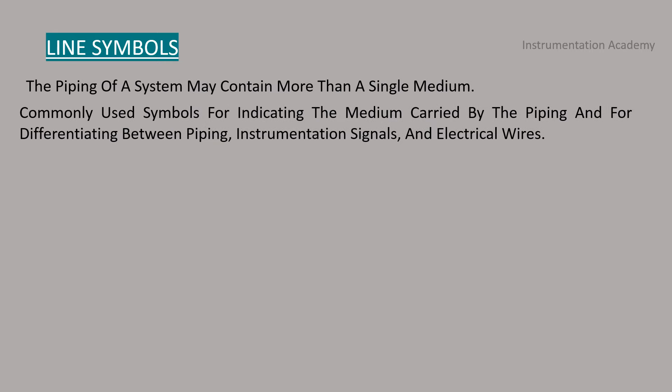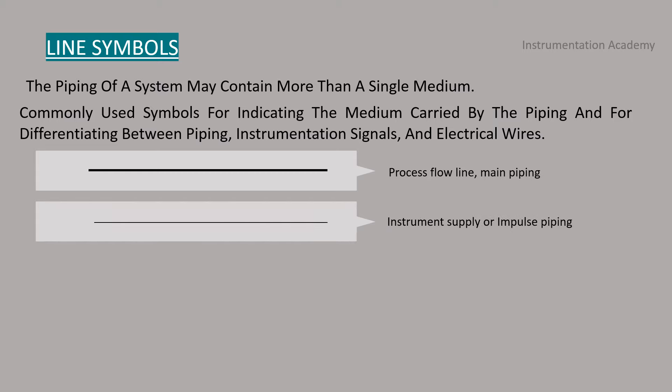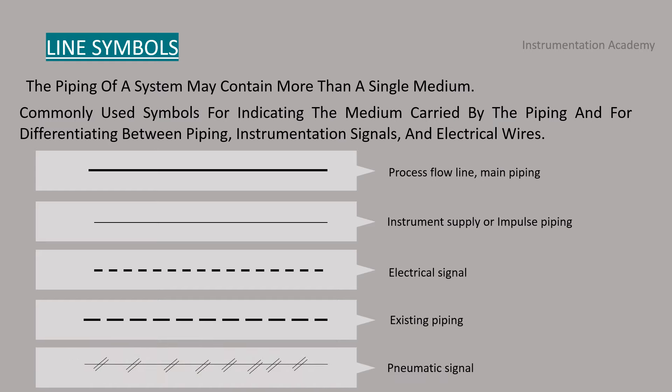The pipe system may contain more than a single medium. These are the symbols used for indicating the medium carried by the piping and for differentiating between piping, instrumentation signal and electrical wires. The most common line type is solid line, which is used to represent main piping. The instrument line or impulse piping is shown by a thin line. A line with short dashes represents electrical signals. A line with long dashes means the pipe is existing in the plant. A line with short double slanting lines represents pneumatic signal, which is the instrument area to control valve or devices.